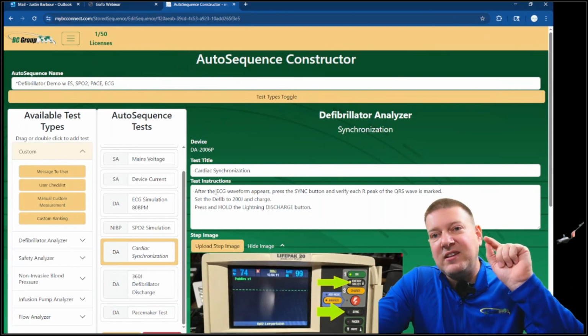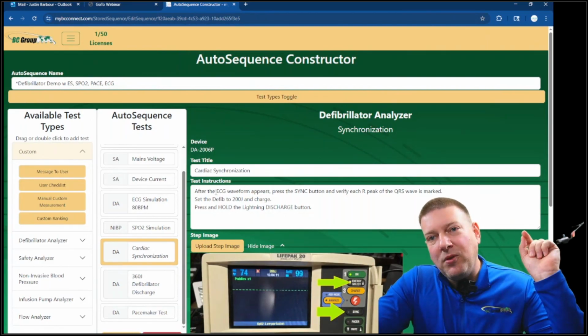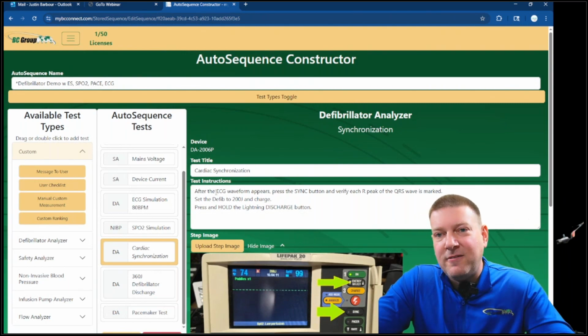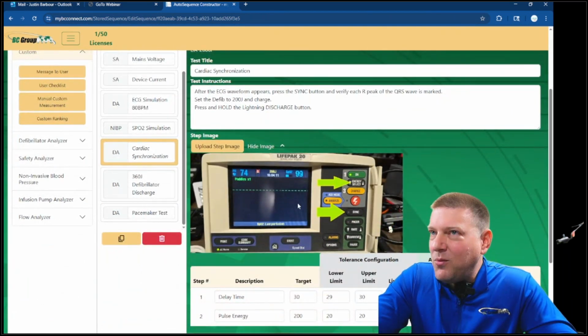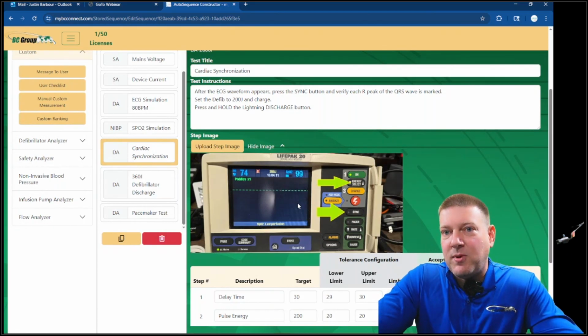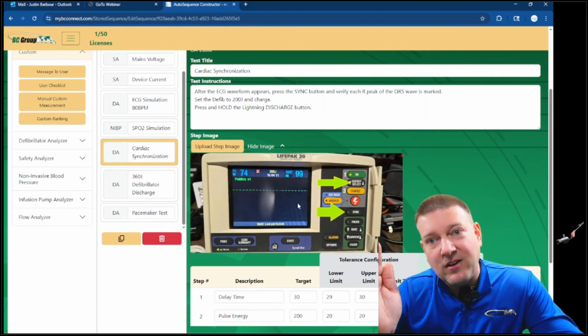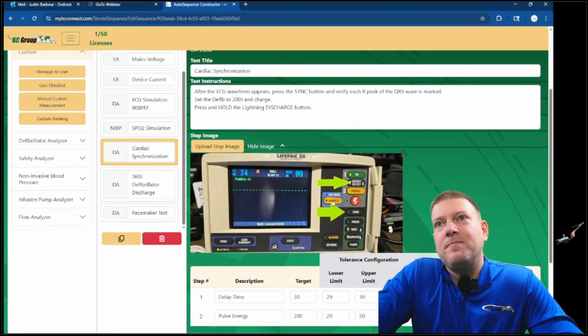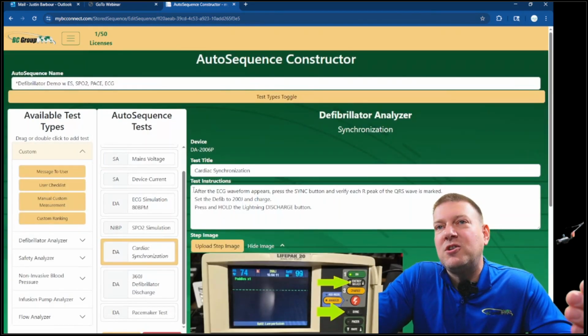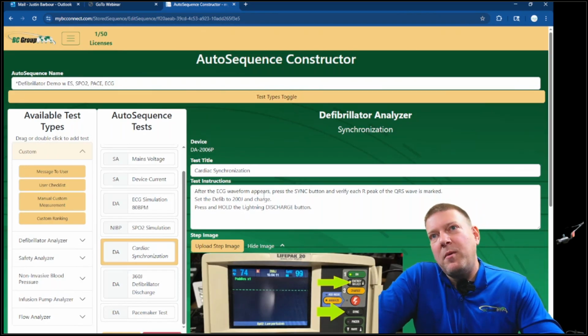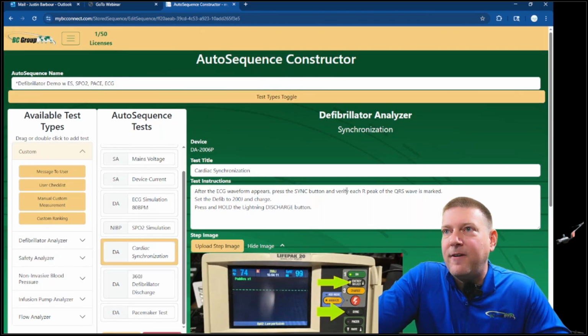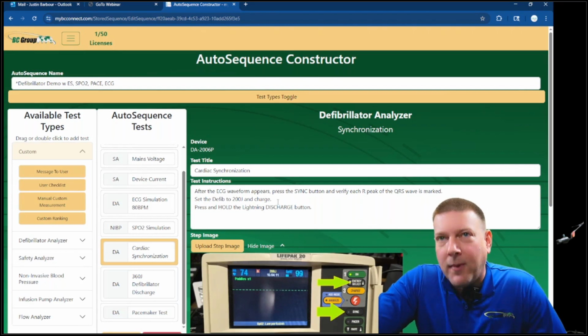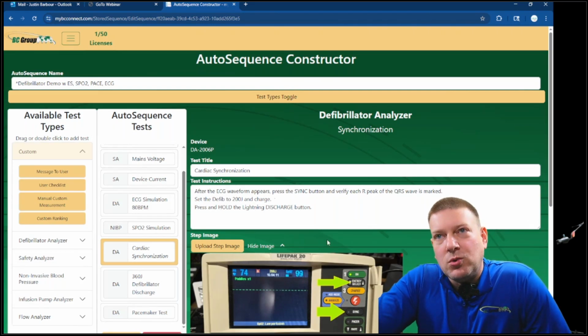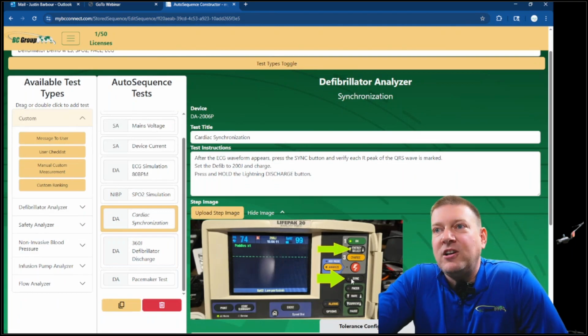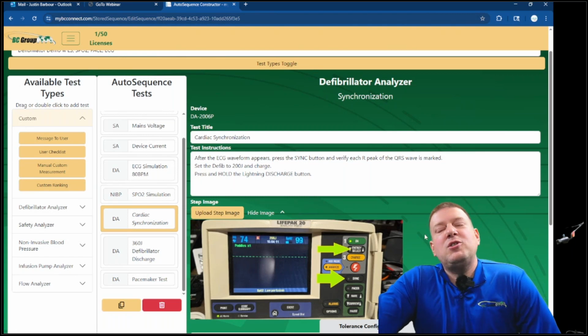cardiac sync because they always hit the discharge button and then they pull their finger off. Well, you guys that have tested enough defibs, you know that it only works by pressing and holding the discharge button until it receives that next synced pulse, and then it discharges. And I give them that specific instruction up here. It says after the ECG waveform appears, press the sync button and verify each R peak of the QRS is marked. Then set the defib at 200 joules, which you can see I showed down here very clearly what buttons they have to press. And I said press and hold the lightning discharge button.